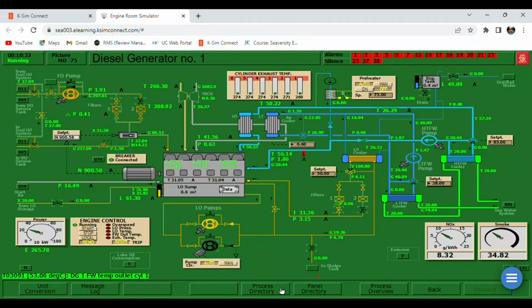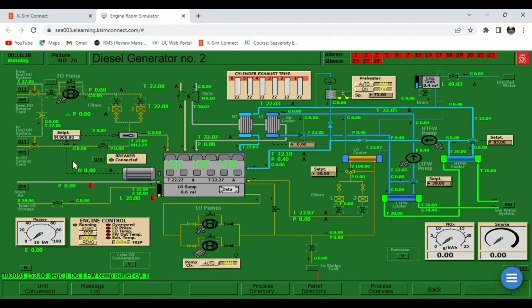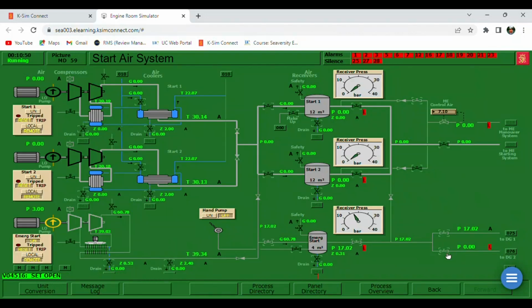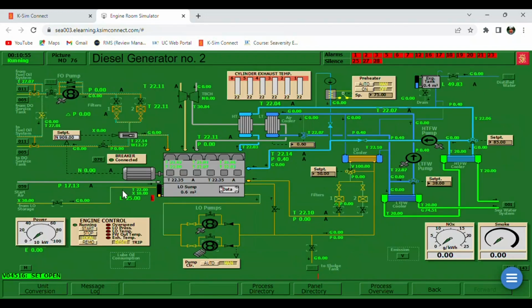The next thing we need to do is set up our diesel generator number 2. Here, the same thing we did on diesel generator number 1: we need to line up the valves and prepare it. For starting air, I'll open this valve and go into DG2. Then top up the lube oil, open this valve, and put the lube oil pump in automatic. Same also with the preheater, put it in automatic. We have already opened the valves going to the diesel generators, right? So we only need to open this shutoff valve, and same also with this valve. Once you have reached the normal level for some tank, you can just close it. Okay, so everything is set up.